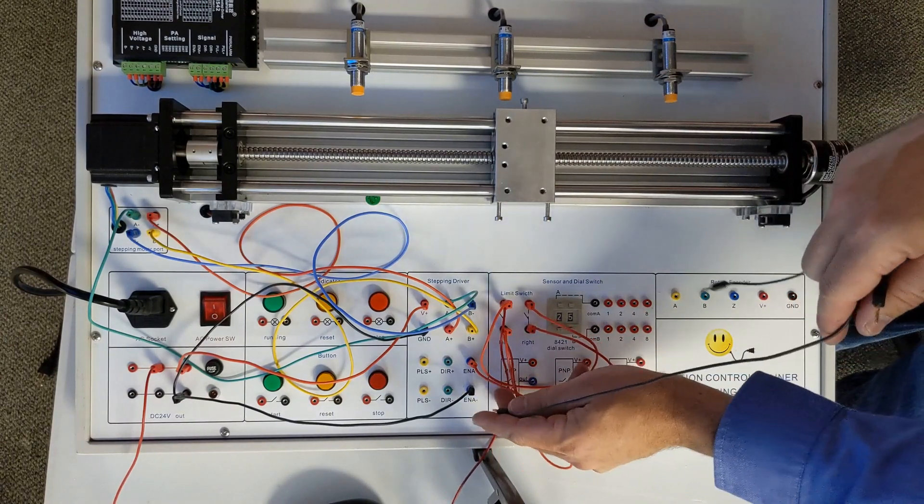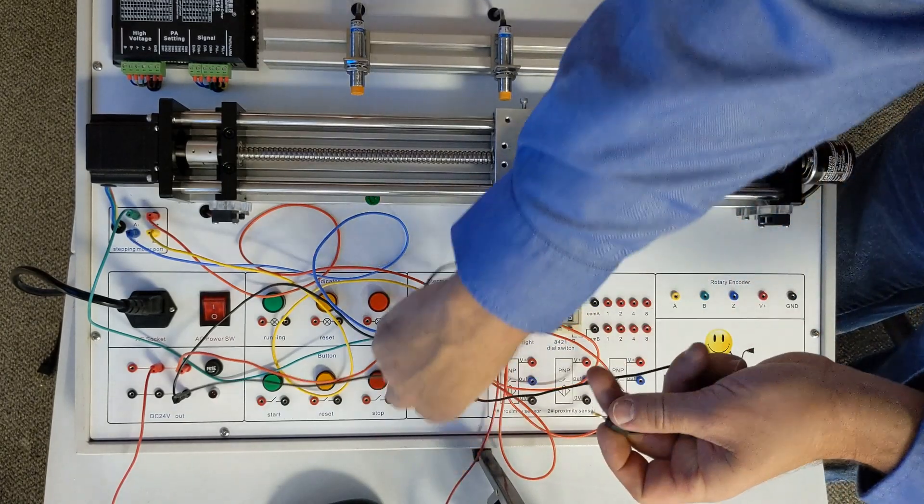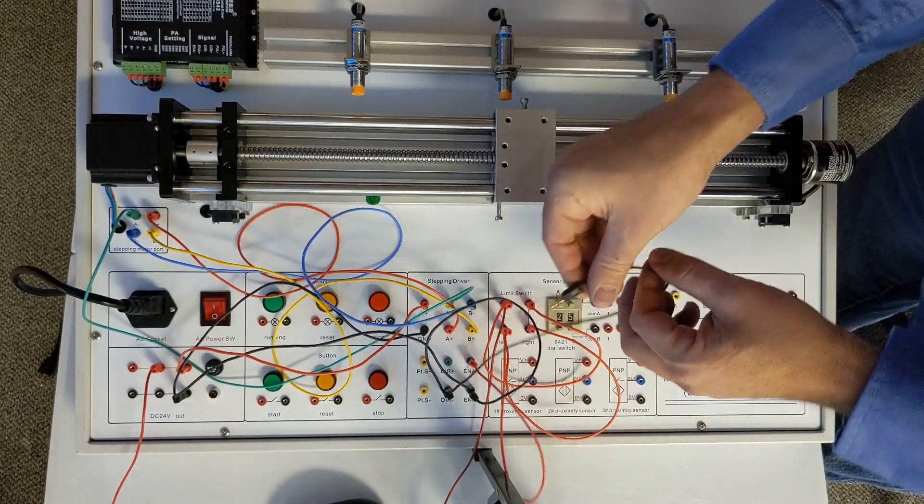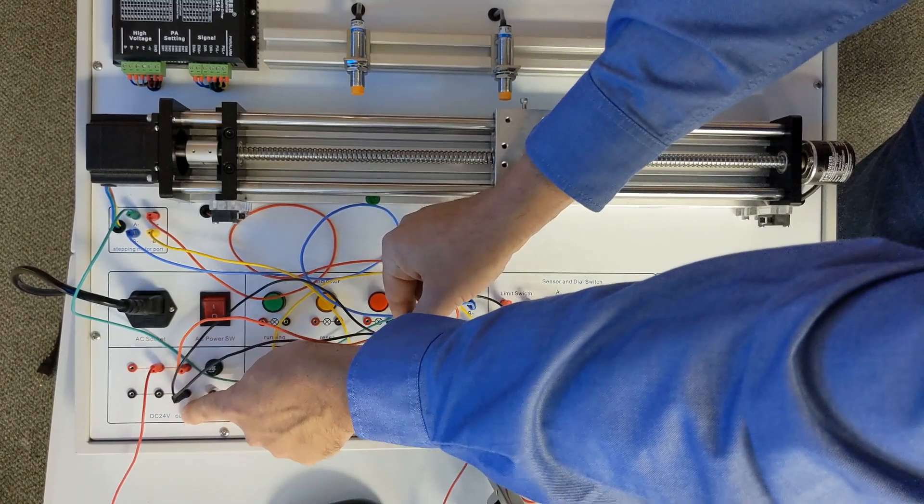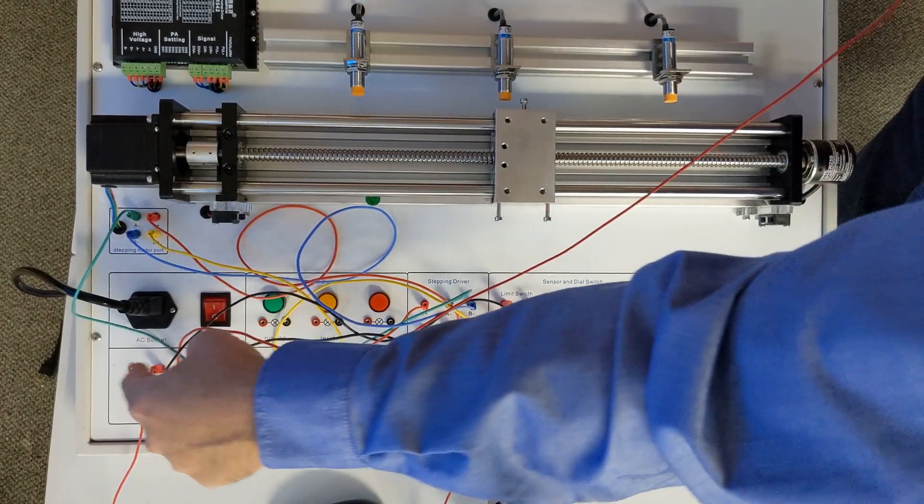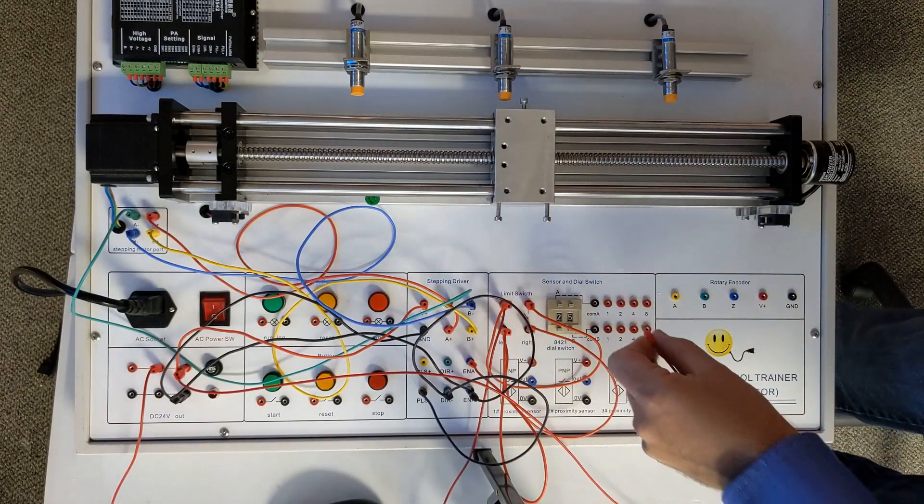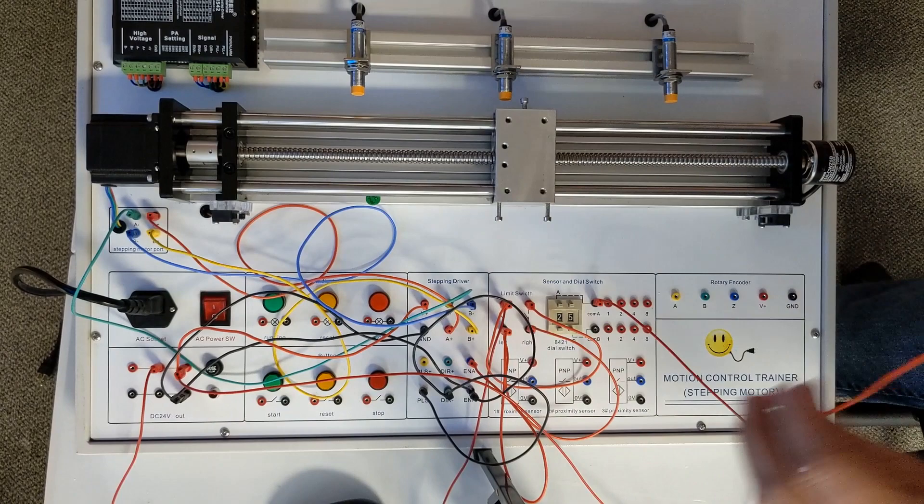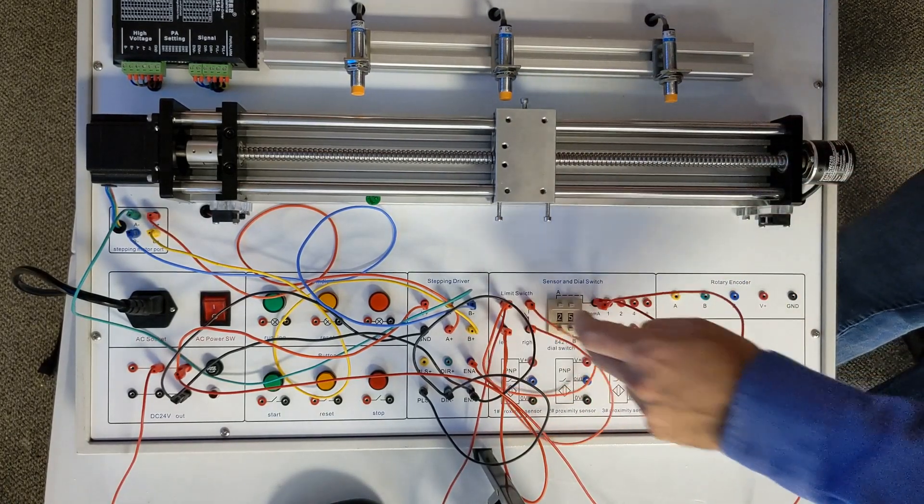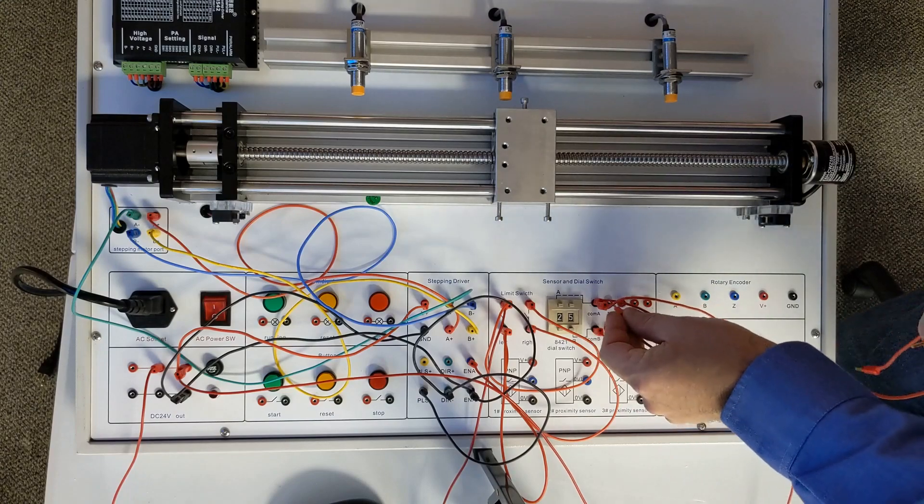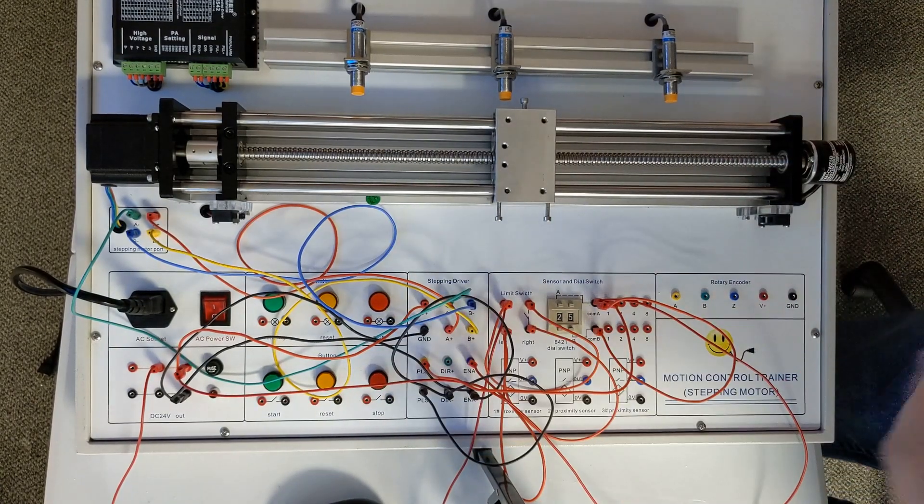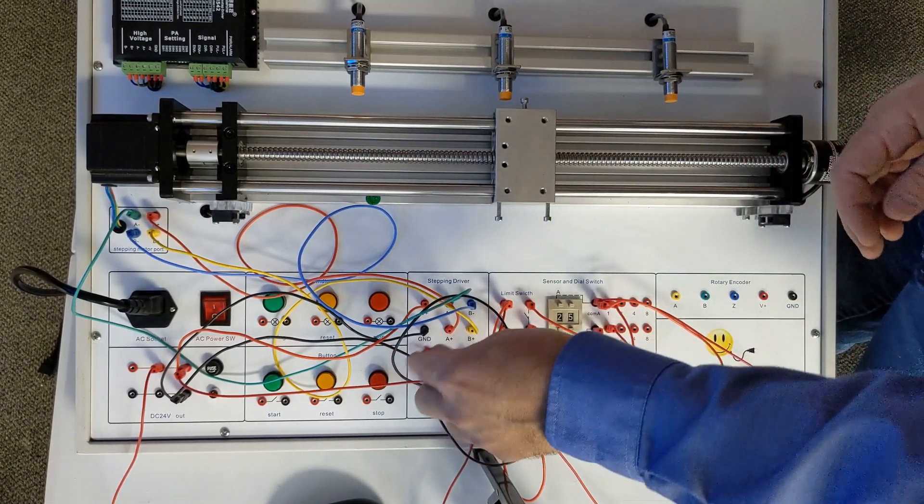Next what we're going to do is jumper the ENA minus to the DIR minus to the PLS minus, so that's going to make all of them connected to the black or the zero volt of our 24 volt. I'm going to take a wire and connect it to the plus 24 volt which is the red set of terminals and connect it to the COM A, then jumper from that COM A to the COM B. That's going to put 24 volt on one side of our contacts. Now I'm going to take a wire from the one of COM A and make that our pulse, and take a wire from the one of COM B and put that on direction.